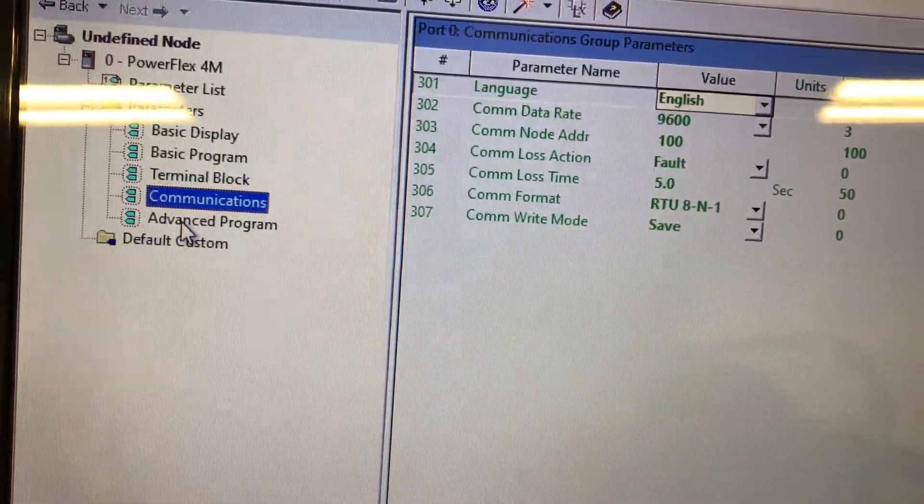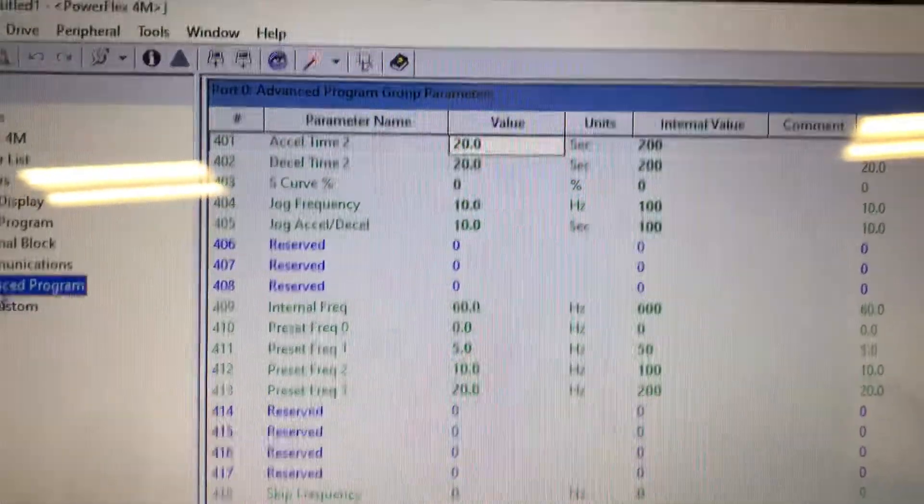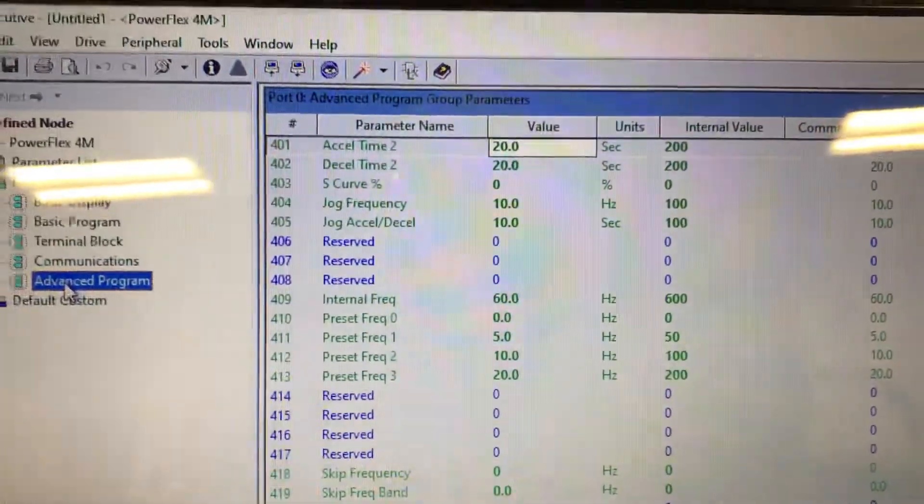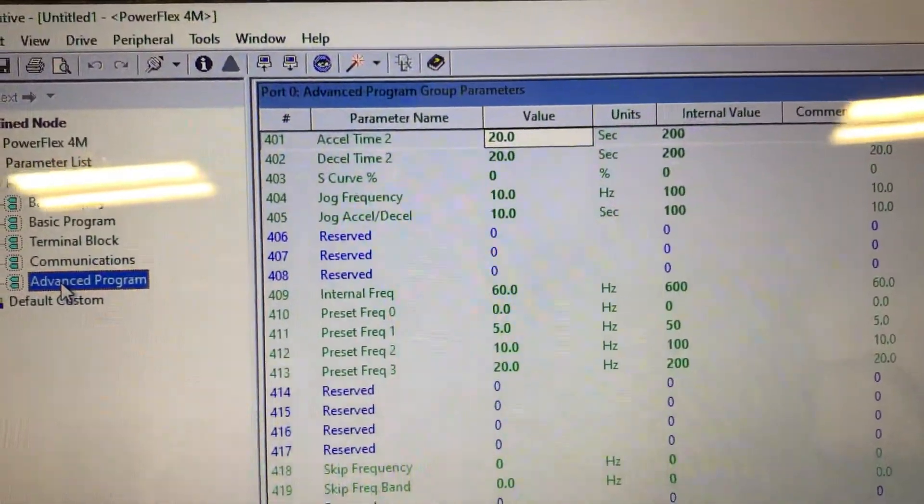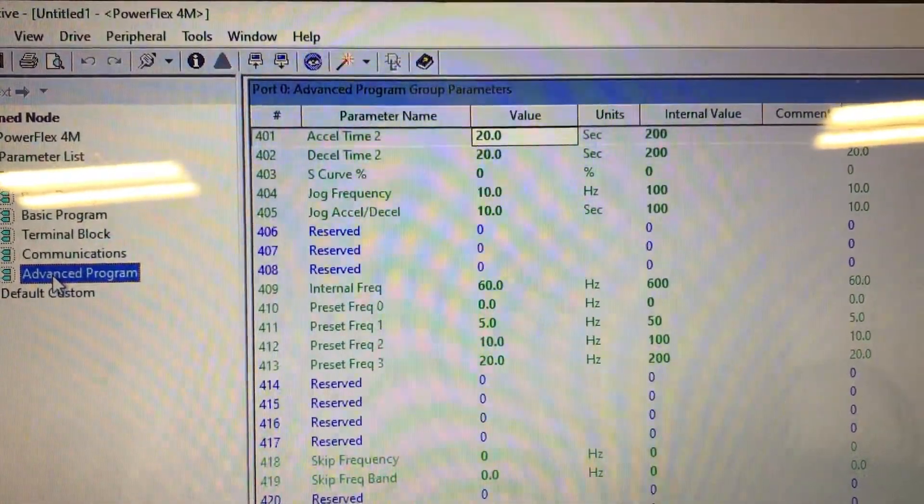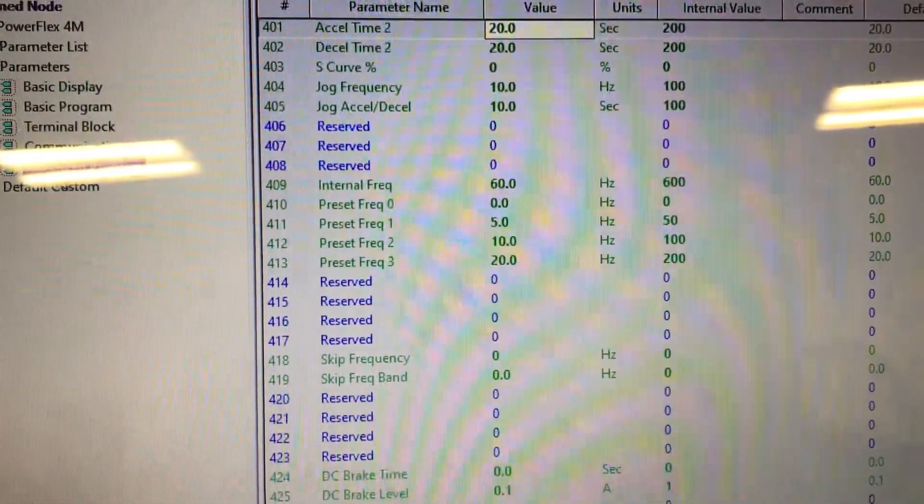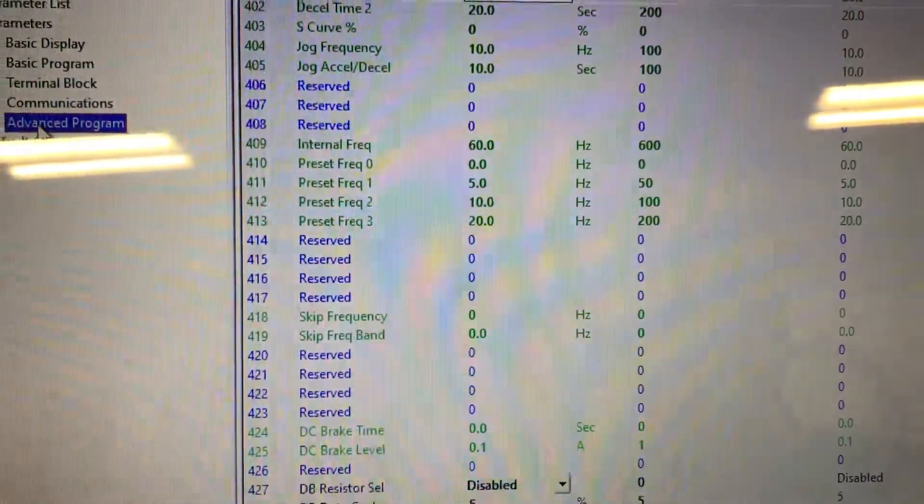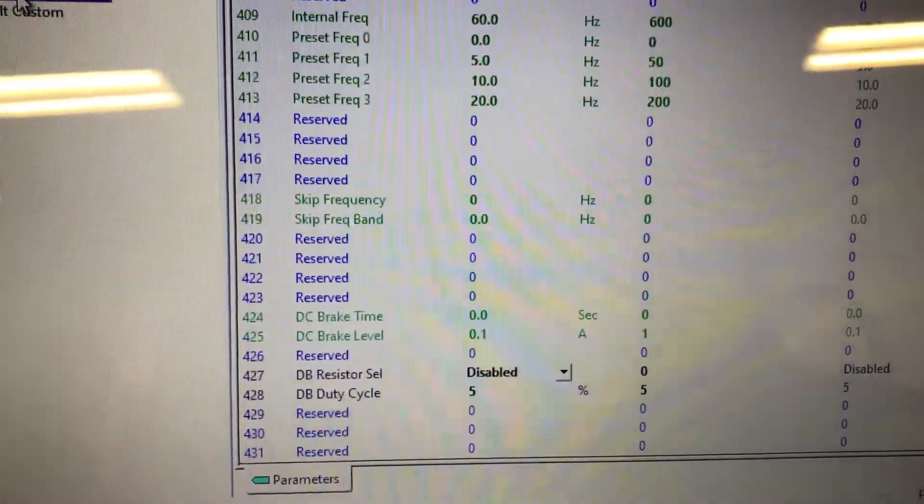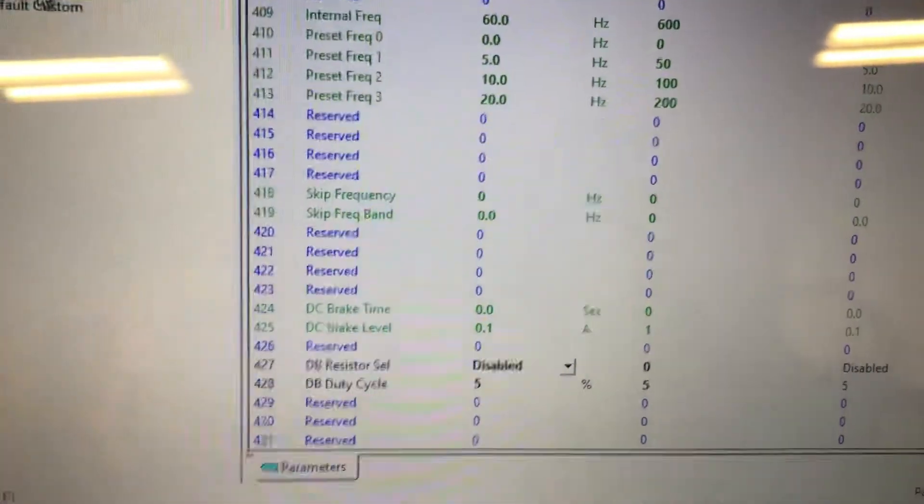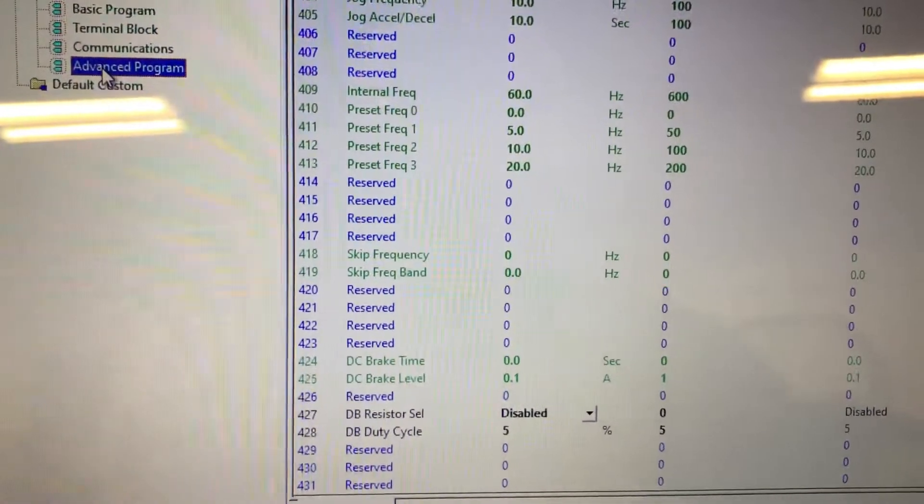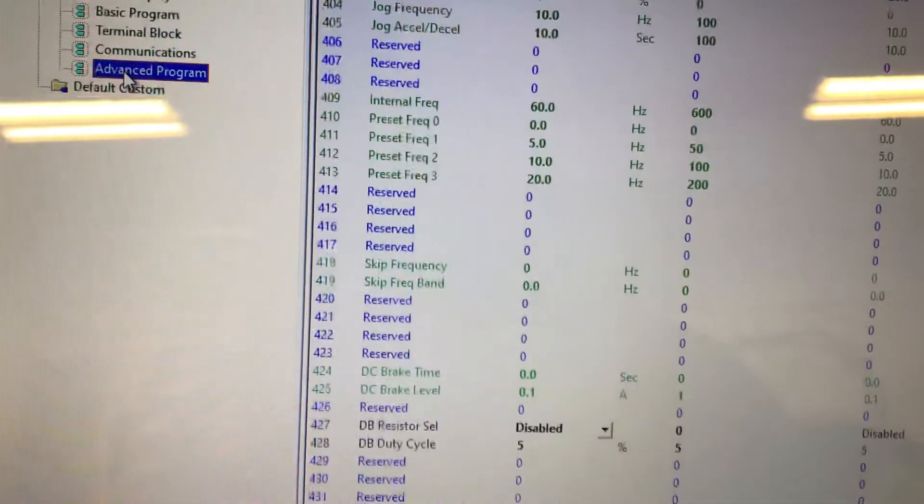Under advanced programming, then there's many programs, because you can tell it to use different accelerates. S-curve, jog, internal, there's preset frequencies that you can select, skip frequencies, DC brake, you can actually tell it to use an internal brake function.